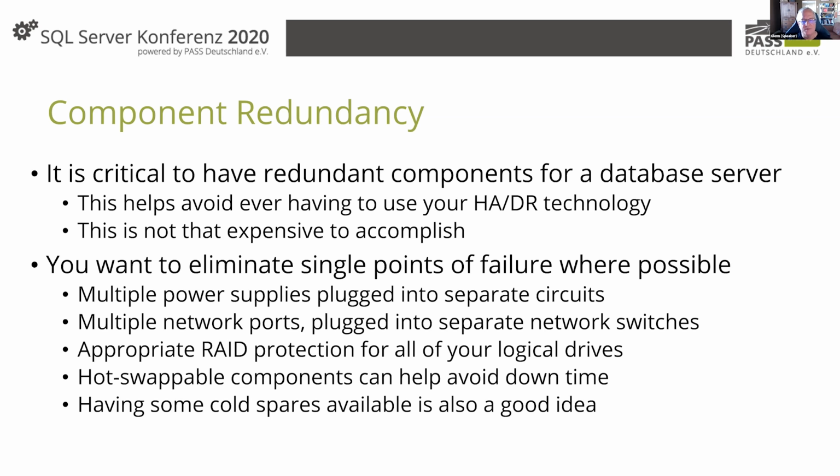A lot of people aren't really into hardware very much, but if you're the DBA, talk to your server people and make sure that they're actually doing this, and go to the data center if you can and look at it, because it's so easy to do dumb things. Like you get a database server with two power supplies, but they're both plugged into the same PDU in the rack. So if the PDU goes down, the server goes down anyways, even though you had two power supplies.